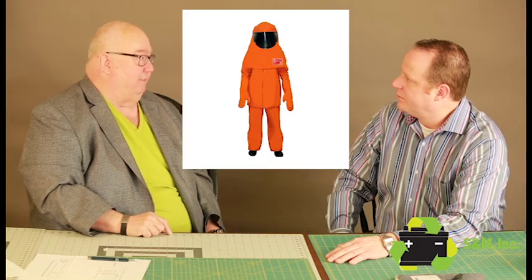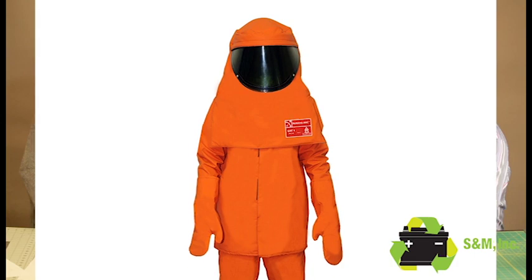Currently, the rules don't want somebody able to put his body across more than 100 volts DC, because of the breakdown point of skin in terms of electric shock. So if you can use disconnect switches for maintenance and break the series string, it might be a 500 volt string, who knows, but if you can break that into increments less than 100 volts, with physical barriers between sections so there's no way you can put your body across more than 100 volts, then you don't have to wear a space suit, these big high cal suits.